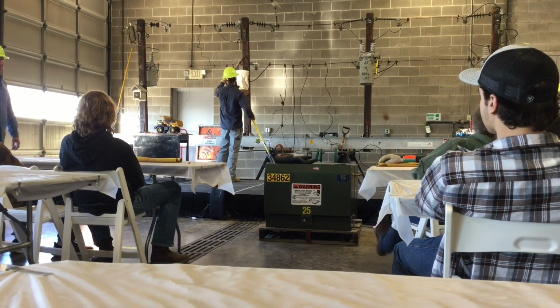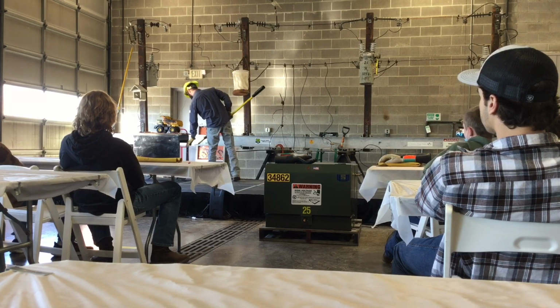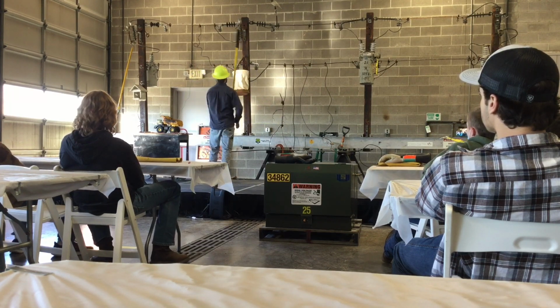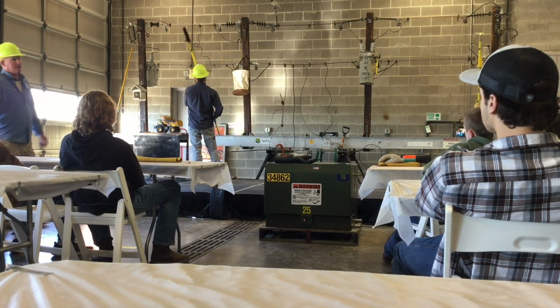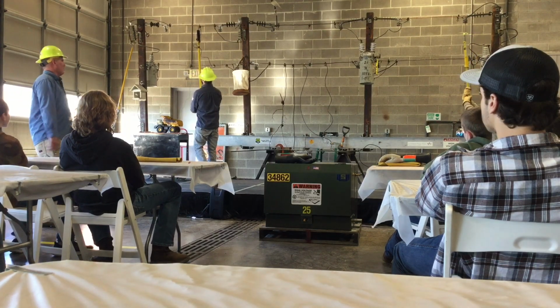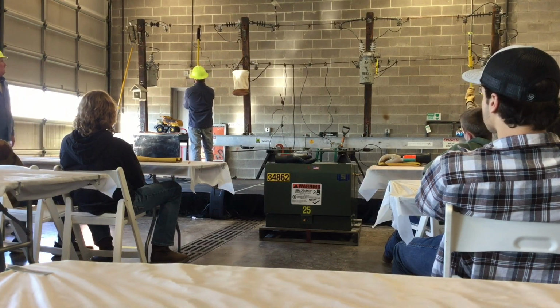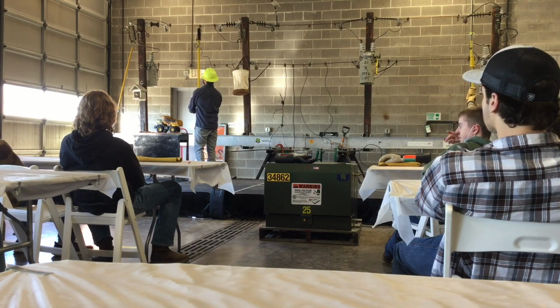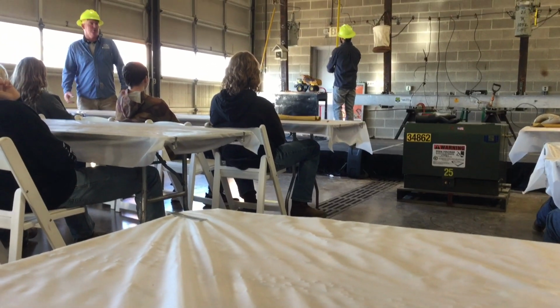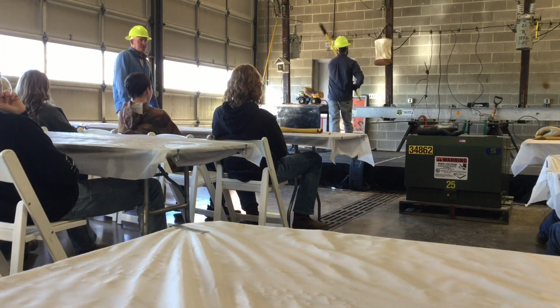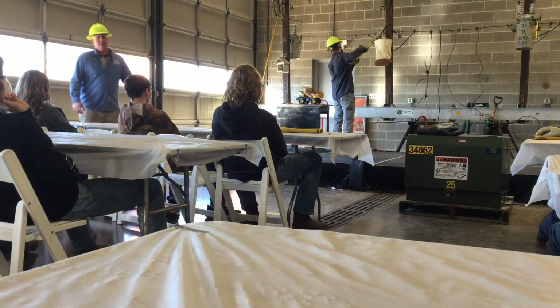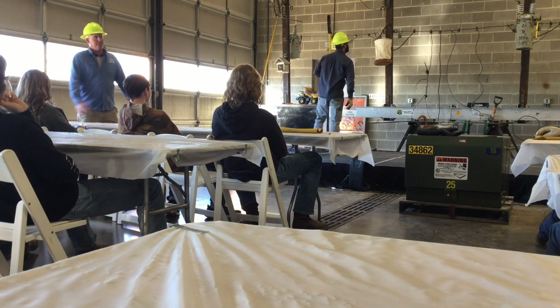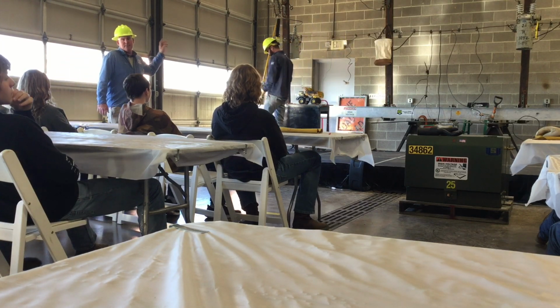So, guys, that is a fuse, and once that fuse blows, you're out of power until we come out there and find the problem, refuse it, throw it back in. And that's about how loud they are. And a lot of times when people call in with no power, they'll say, hey, somebody shot a shotgun right outside my door, and I think my transformer blew up. But more times than not, that's a fuse that's blowing. It's not the transformer.